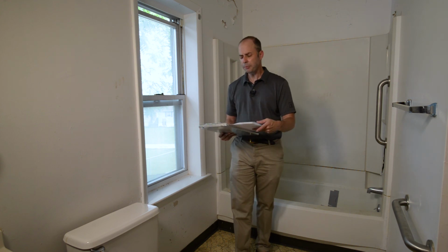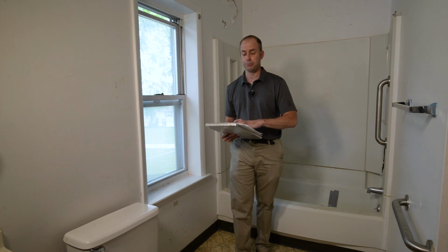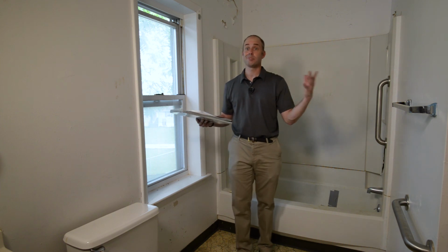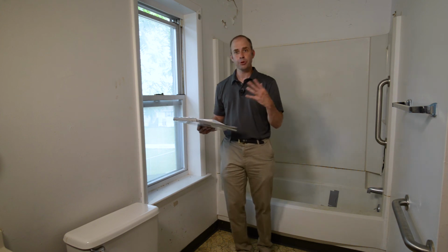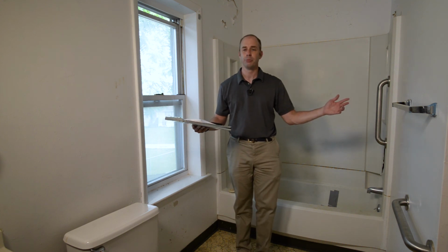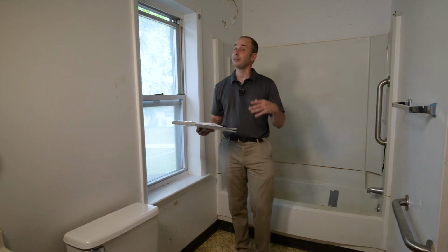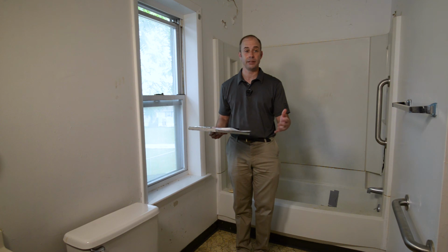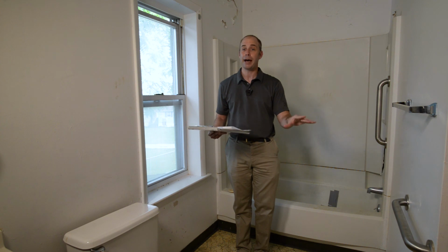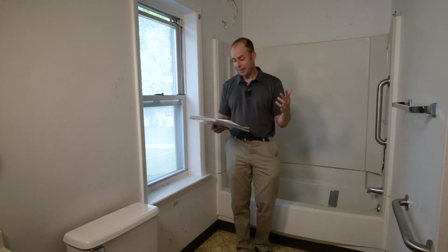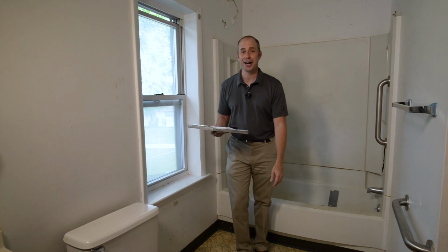One that we typically have, even though this is a small bathroom with one outlet in here, is that Hagerstown, like I said, is unique, and sometimes when it was built, there was not indoor plumbing inside those residences. So the question we get is, if this is a really large bathroom and I have multiple outlets in that bathroom, do they all need to be ground fault protected? The answer to that question is yes. Any outlet in a bathroom needs to be ground fault protected. No matter if it is 10, 20 feet away from a fixture, any outlet in a bathroom must be ground fault protected.